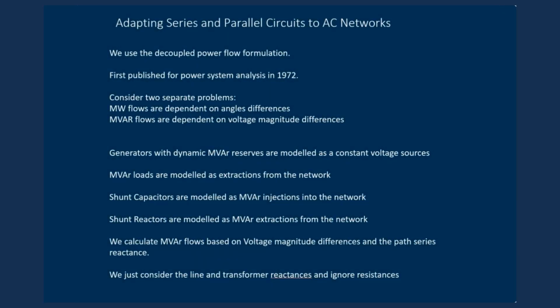So now let's look at how we adapt the series and parallel concepts in the DC networks to apply to an AC network. To do this, we'll use the decoupled power flow formulation. This was first published by Dr. Brian Stott in 1972. In this formulation, we consider two separate problems. We consider that the megawatt flows are dependent on the angle differences. And we consider that the megavar flows are dependent on the voltage magnitude differences. As power system operators, we talk about how megawatts flow downhill on the angle difference. We also talk about how megavars flow downhill on the voltage magnitude difference.